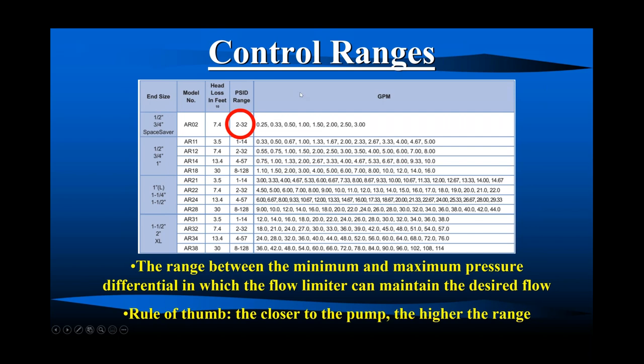If you have a pump set that's 100, well, maybe the flow limiters closest to that pump, maybe two floors, three floors up or down, depending where your pump is, maybe we get a 4 to 57 PSID range. Please note that the head loss in feet is 7.4. That's what we plug in your head calc for your pump. If it's 10 stories and a 100-foot TDH pump, 4 to 57 on the first two stories, and the rest are 2 to 32.